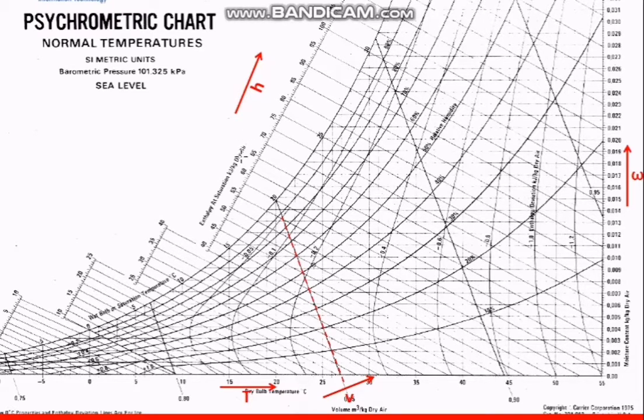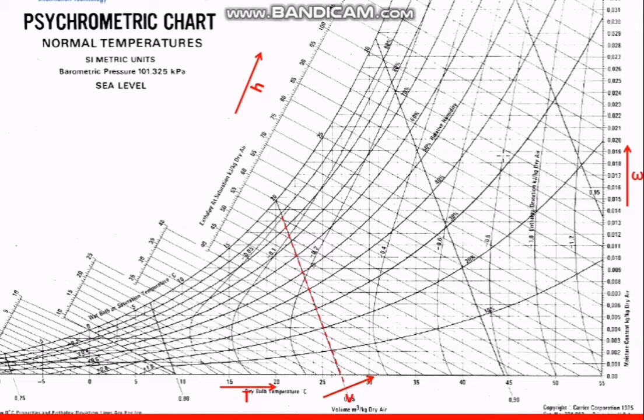The enthalpy at saturation lines follow a diagonal pattern across the chart. We can be given any two values to locate a point — such as relative humidity and dry bulb temperature, or the humidity ratio — and then read off the other properties from that point.